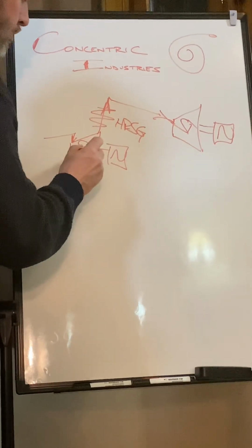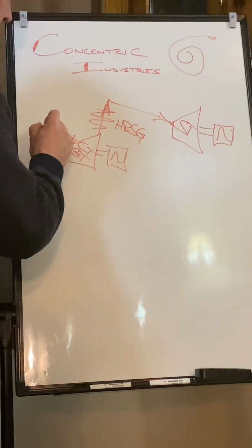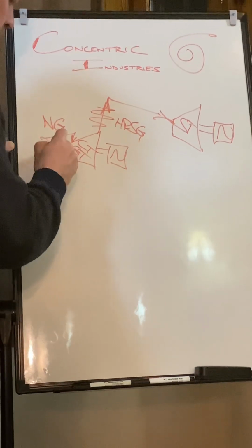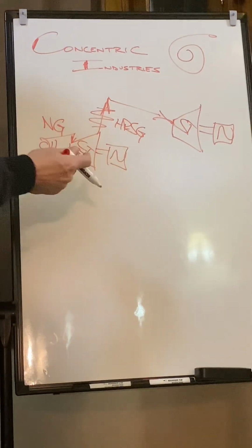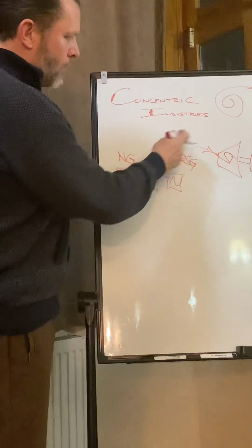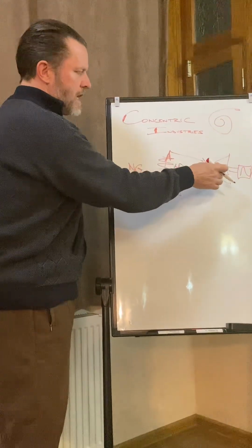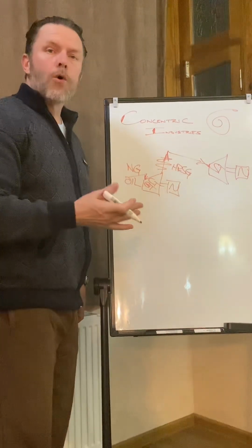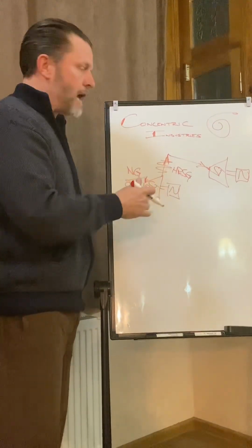This is called a combustion turbine or gas turbine. So you have natural gas or oil coming in here. This is what's called the air standard Brayton cycle. Then you run through the steam production from the waste heat into an additional steam turbine for more power generation. So you get more efficiency, you get more output without extra fuel.